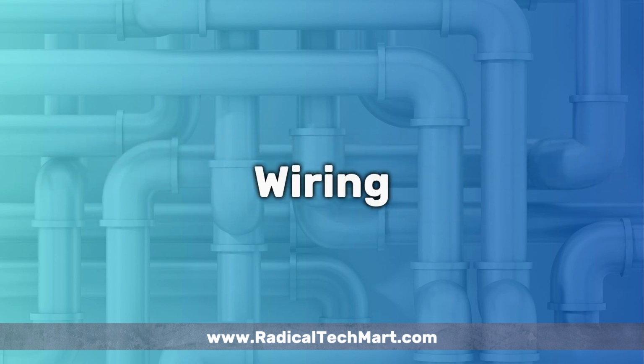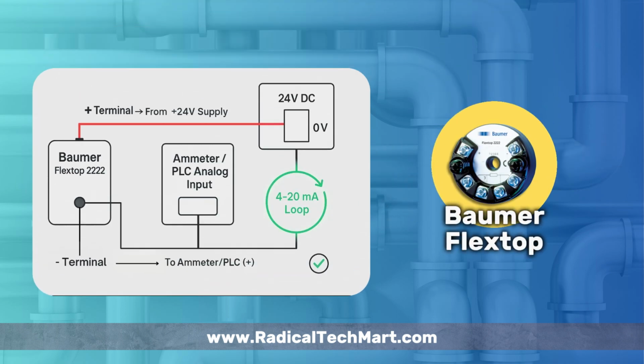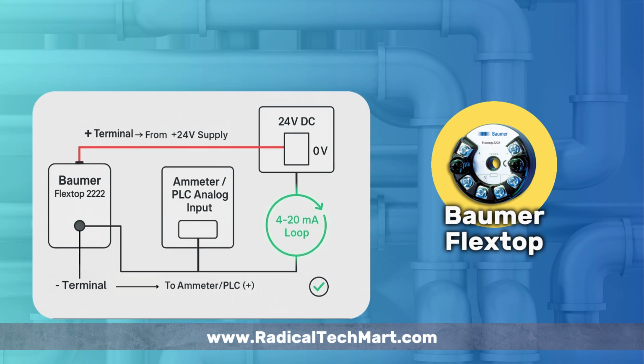Let's begin the wiring. First, connect the positive terminal of the 24-volt DC supply to the plus terminal of the Flextop transmitter. Connect the minus terminal to the positive side of your indicator or PLC analog input and return the loop back to the supply's negative. This forms a standard 2-wire 4 to 20 mA loop.